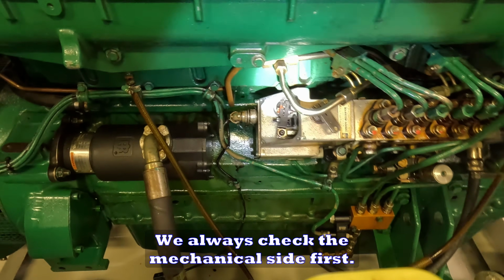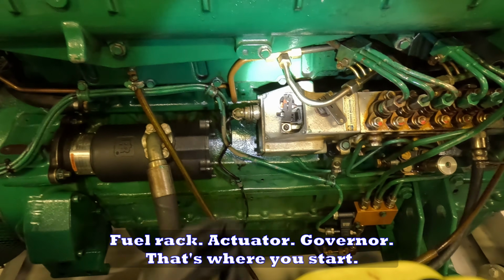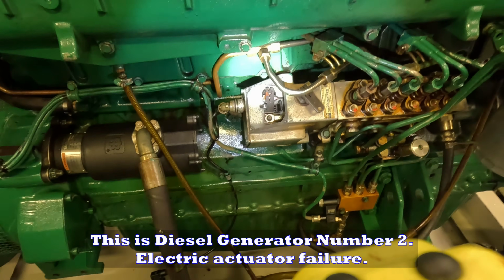check the mechanical side first, not the AVR, not the excitation system. The mechanical side: fuel rack, actuator, governor. That's where you start. This is diesel generator number 2, electric actuator failure.